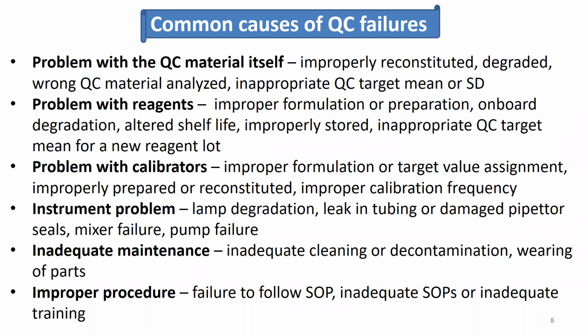QC can fail due to a problem with the reagents. So perhaps the reagent is improperly formulated by the manufacturer or improperly prepared by the laboratory. Reagents can exhibit onboard degradation or degradation during their shelf life when stored at their storage condition. Reagents may be improperly stored, or the lab could be using an inappropriate QC target mean for a new reagent lot. QC failures can also be caused by problems with calibrators, so improper formulation or target value assignment by the manufacturer. The lab could improperly prepare the calibrators, or the lab could be using an improper calibration frequency.